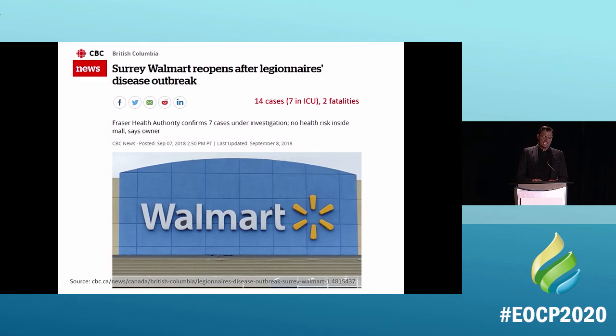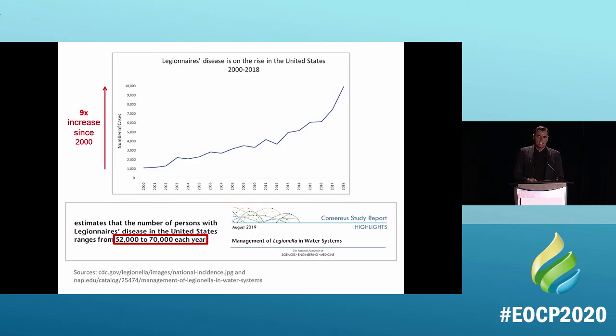Closer to home, Surrey, a couple of years ago, had a Legionella outbreak with 14 cases. Seven went to ICU, and two people died. Unfortunately, if you Google Legionella Surrey, Walmart comes up. Walmart was proactive, they shut down their cooling systems, scrubbed and cleaned, but the actual culprit was a cooling tower that belonged to the Civic Library. It's just unfortunate the way it gets reported, because if you Google Surrey Legionella outbreak, it's going to point to Walmart, when it wasn't Walmart that caused it.